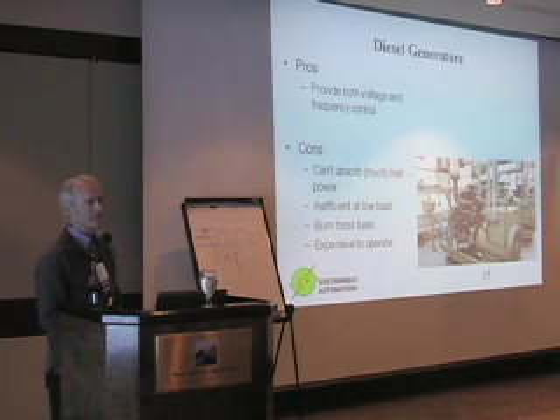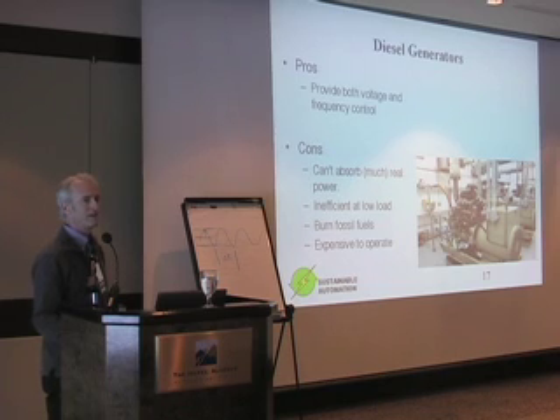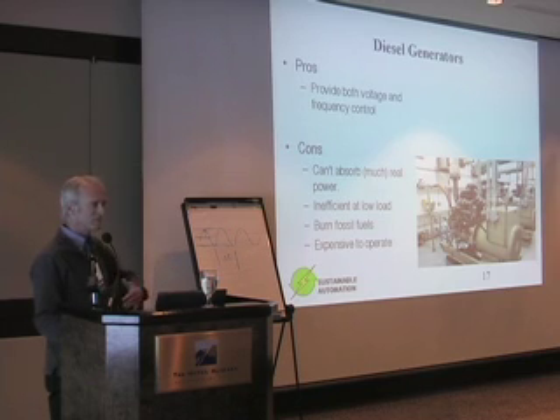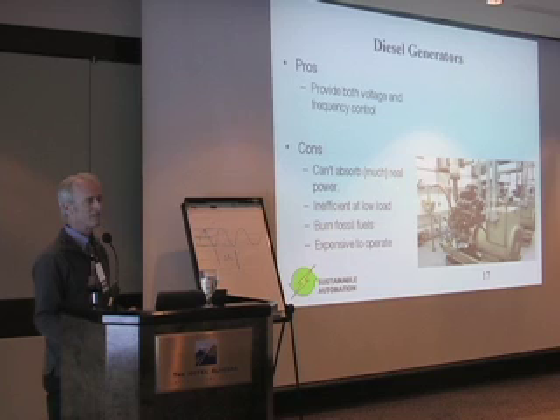Diesel gensets, they do the job, and they do the complete job. They control voltage and frequency, and they do that by ensuring this balance on a real-time basis of real and reactive power. The real power is addressed with the throttle. There's a speed control on that genset. If the frequency starts to drop, they inject more fuel. It injects more real power into the system.